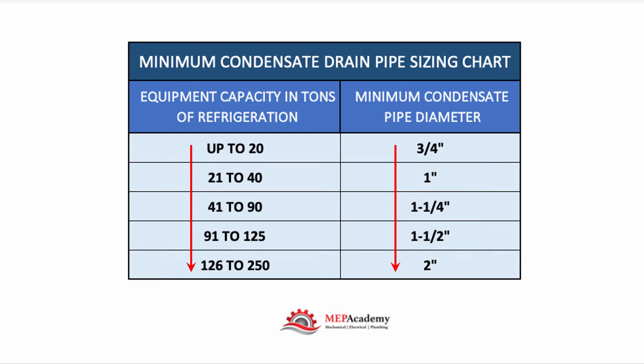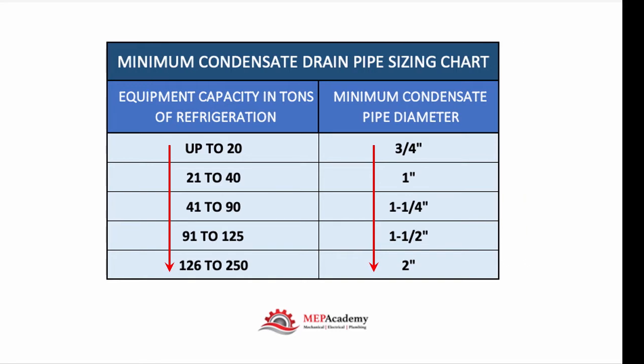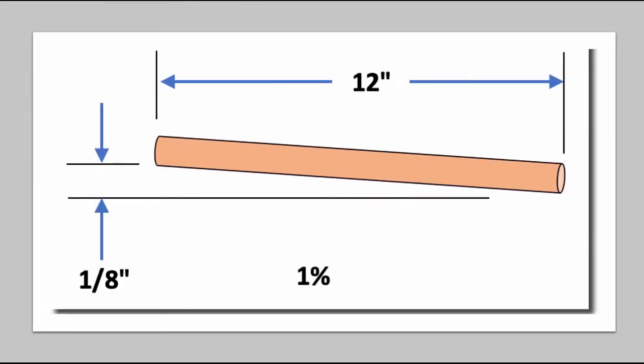As you accumulate more tonnage tied into your main condensate pipe, you will increase the size. The pipe needs to be sloped an eighth inch per foot, or one percent — that's an eighth inch every 12 inches — to make sure that the condensate keeps moving.